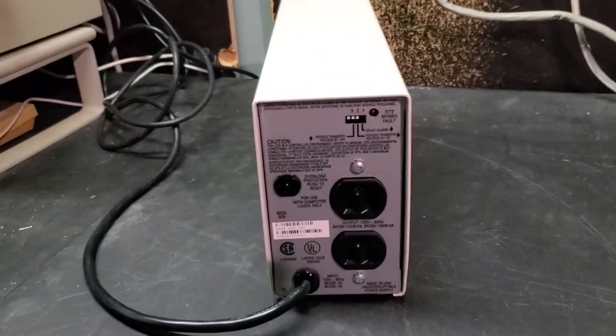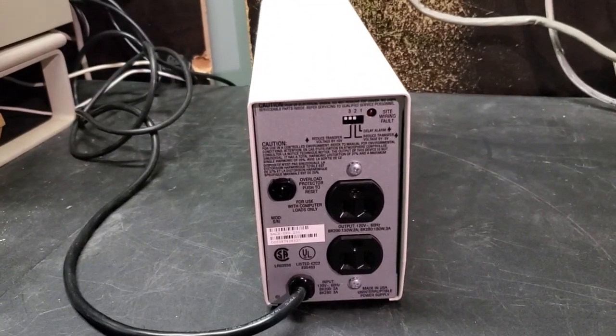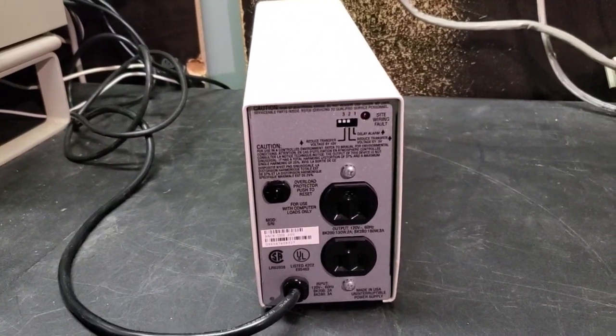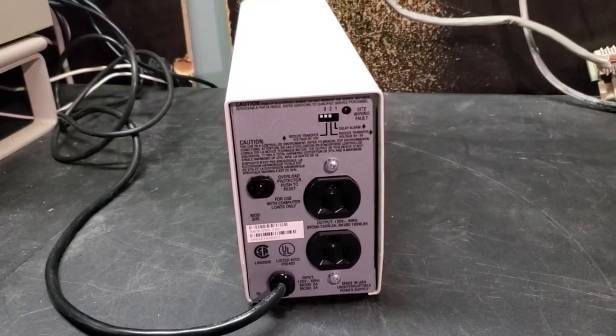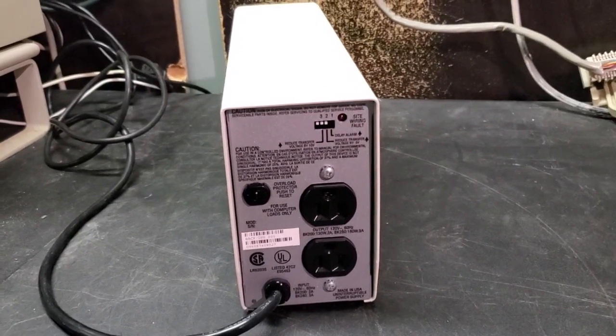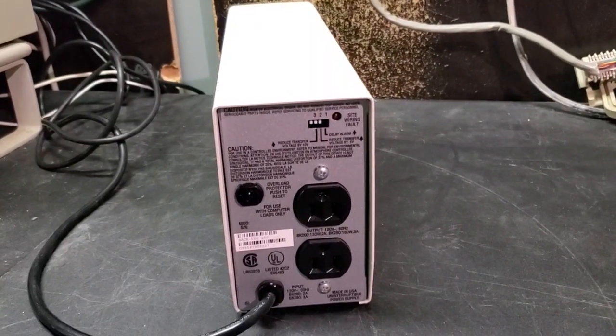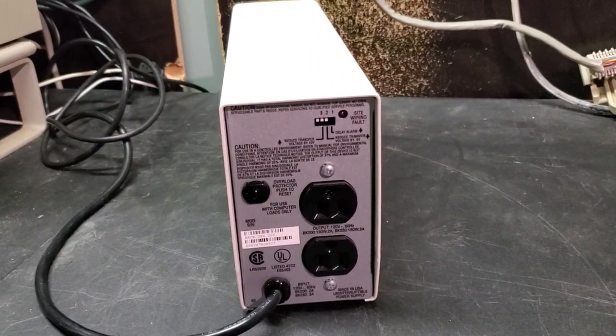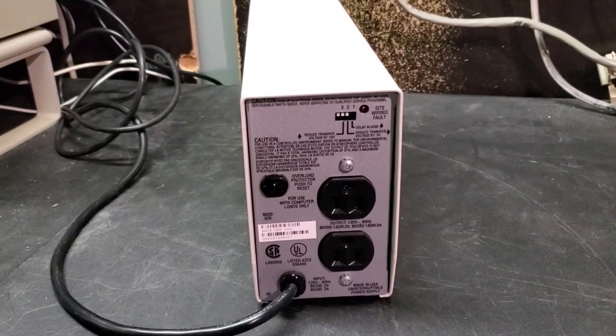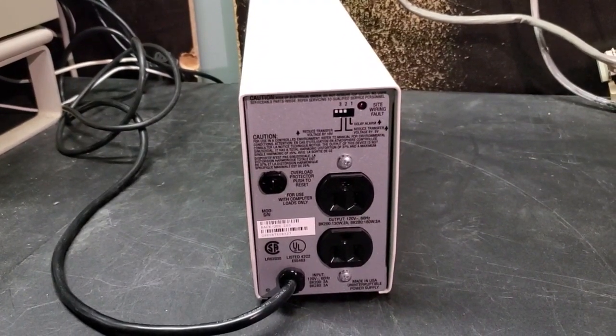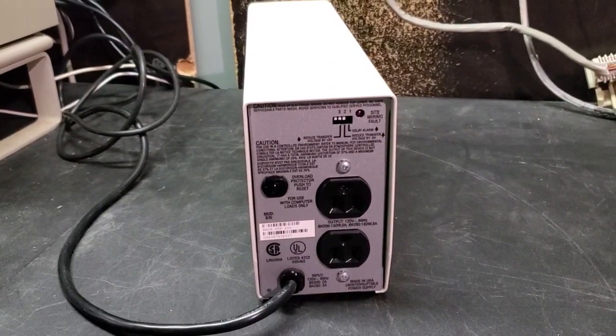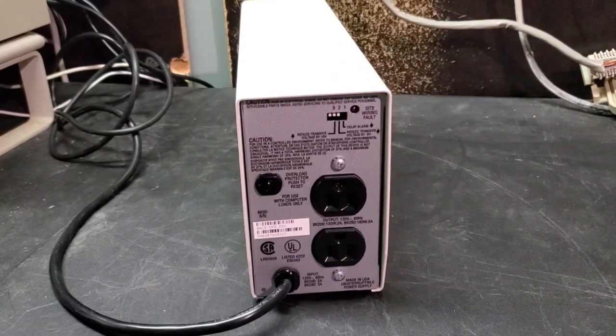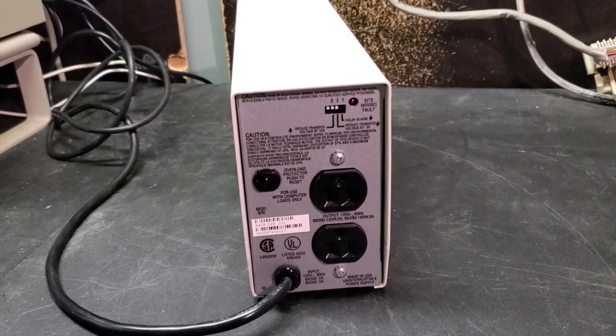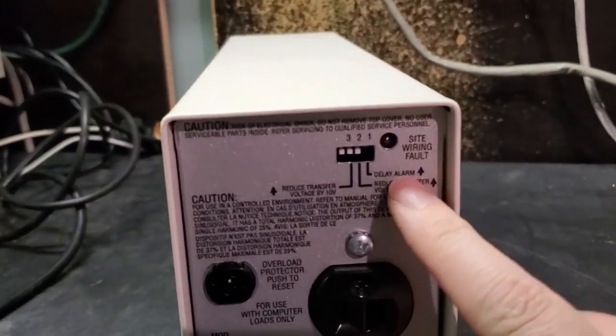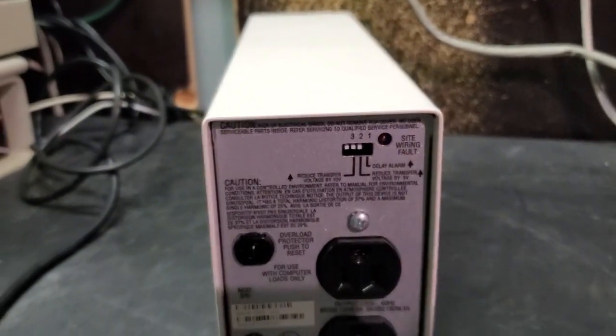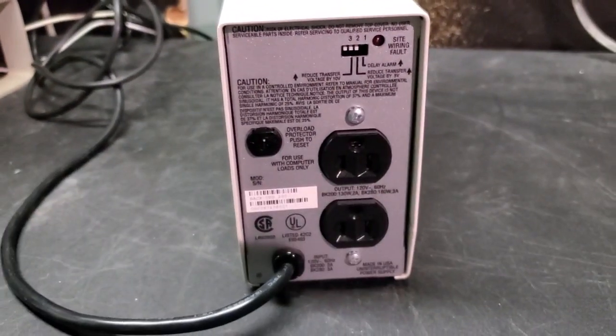There is a piezo buzzer in this thing. When the power goes out, it will alarm, and there's no way to shut it up, and it is extremely loud. It is so much louder than a smart UPS. It's basically as loud as a smoke alarm. That's how loud the buzzer in this thing is, and I don't understand. So I did what I've actually heard of quite a few people doing with these if they use them. I just desoldered the buzzer altogether. I got rid of it, so this thing has no beep anymore. But if I had left it intact, we have a switch here to delay the alarm versus the alarm starting immediately after power goes out.